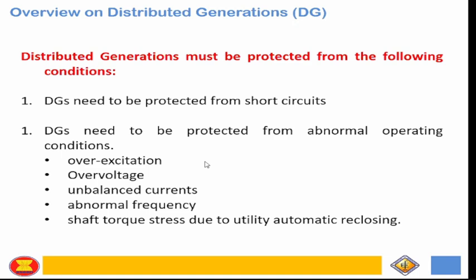As experience, no? One of my experience, yung sa 242 megawatt at Navotas power plant, sa diesel power plant, it's composed of 42 generators, no? Yung nag-load test kami, and then we have that negative sequence protection or device 46. During load test, palaging nag-a-assert yung negative sequence over current protection because of one of the scenario, no, na bakit siya mag-assert because of the unbalanced current, no.